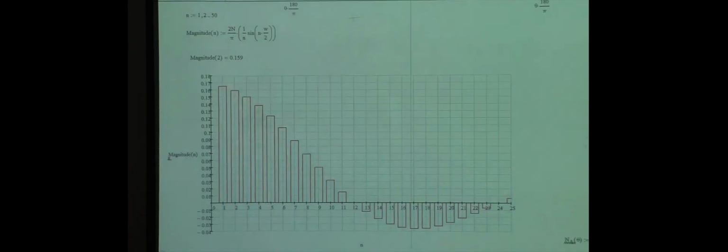The concentrated winding has a very rich source of harmonics. That is going to create a lot of eddy current and hysteresis losses if you're not careful with the design.